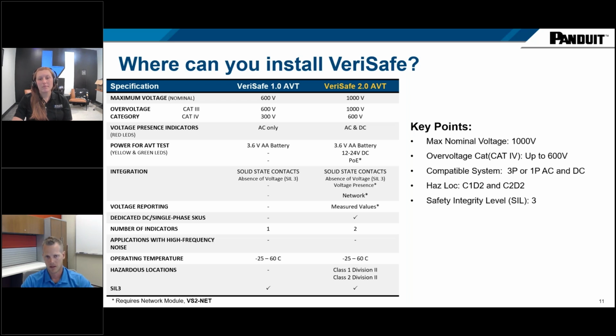And then safety integrity level of 3, which I'll point out that portable meters don't have a SIL3 rating, indicators don't have a SIL3 rating, and the test stations don't have a SIL3 rating either, because it's just not a tested and designed product to the same level as an absence of voltage tester.